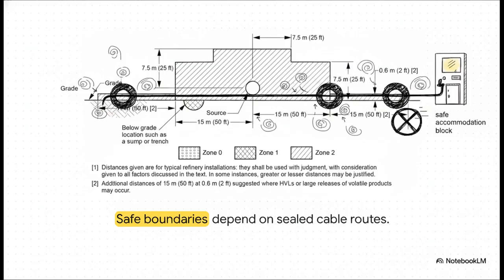Moving along, as our cable travels across the facility, it obviously crosses physical zone boundaries. Safe physical boundaries depend entirely on sealed cable routes and adequate ventilation. Because the cable physically crosses from, say, a hazardous zone into a safe control room, the route itself can accidentally become a superhighway for flammable gases. We absolutely have to meticulously seal that route, so gas physically cannot travel along the outside of the cable jacket or through the conduit into a safe area.